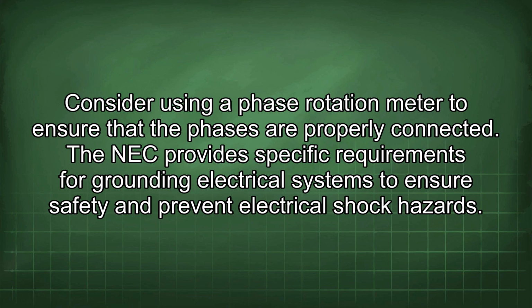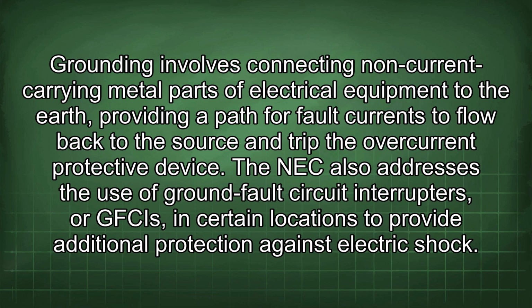The NEC provides specific requirements for grounding electrical systems to ensure safety and prevent electrical shock hazards. Grounding involves connecting non-current carrying metal parts of electrical equipment to the earth, providing a path for fault currents to flow back to the source and trip the overcurrent protective device. The NEC also addresses the use of ground fault circuit interrupters, or GFCIs, in certain locations to provide additional protection against electric shock.